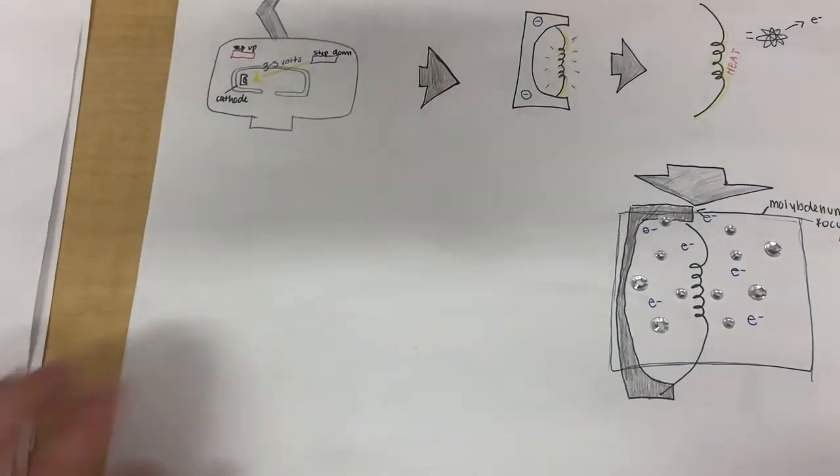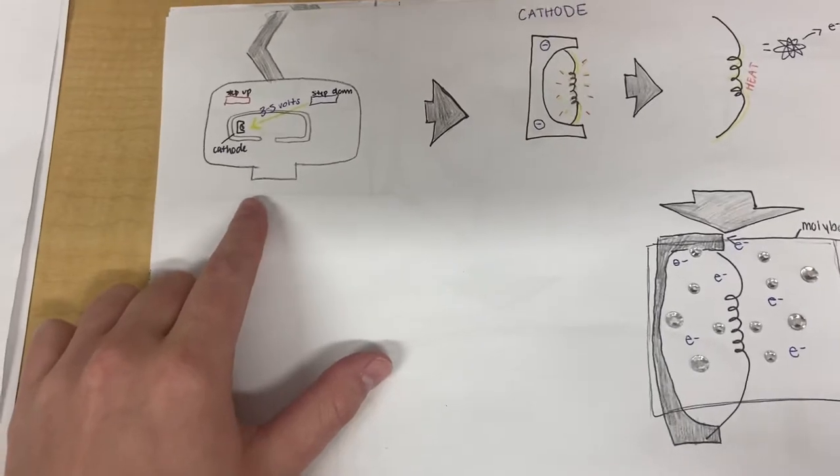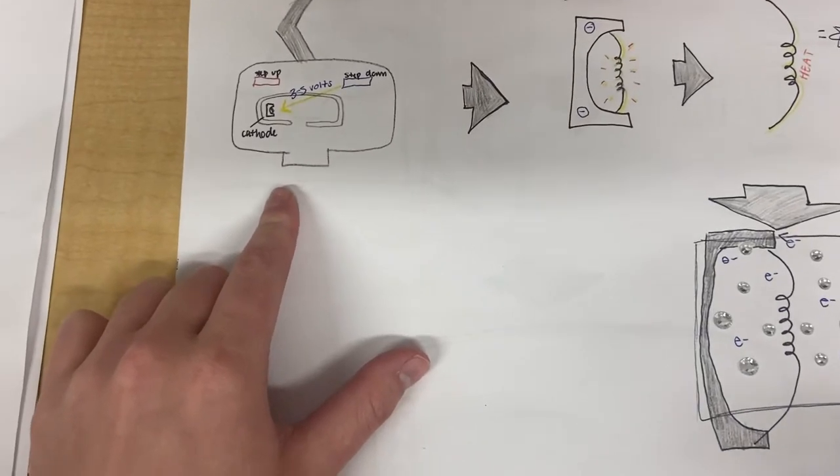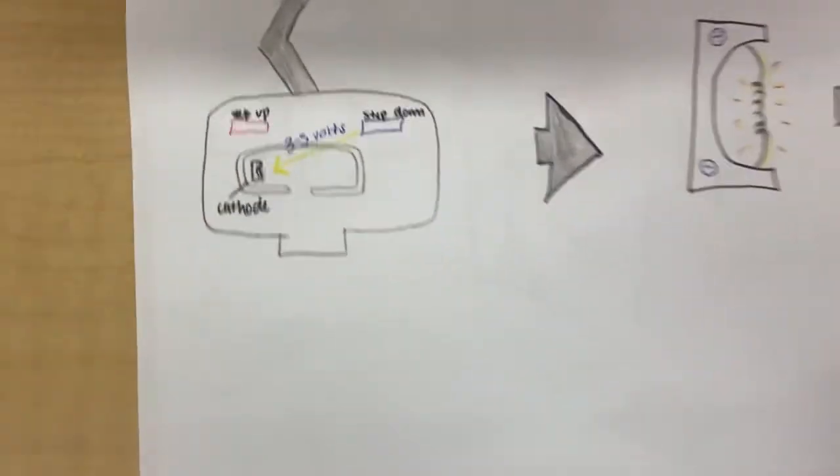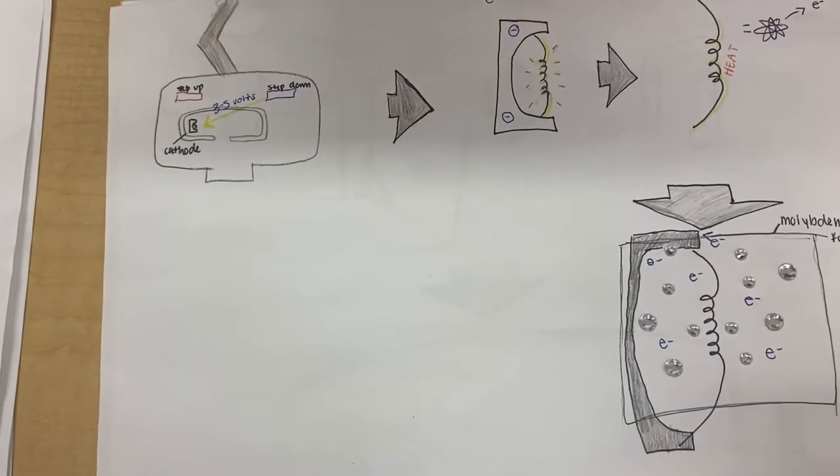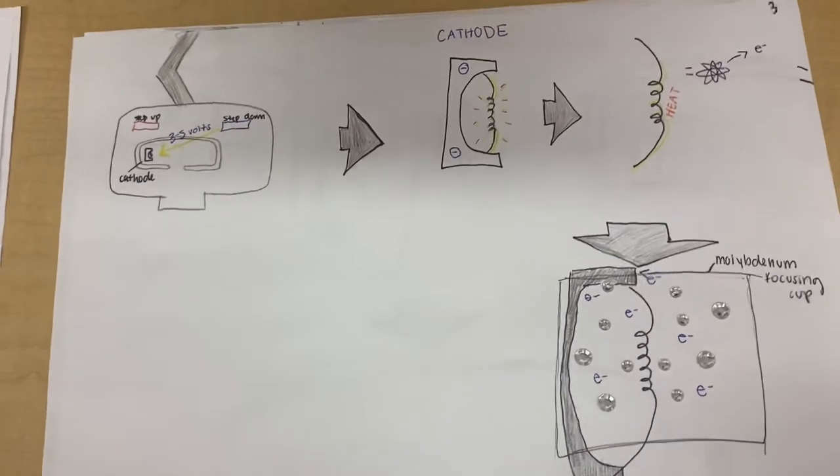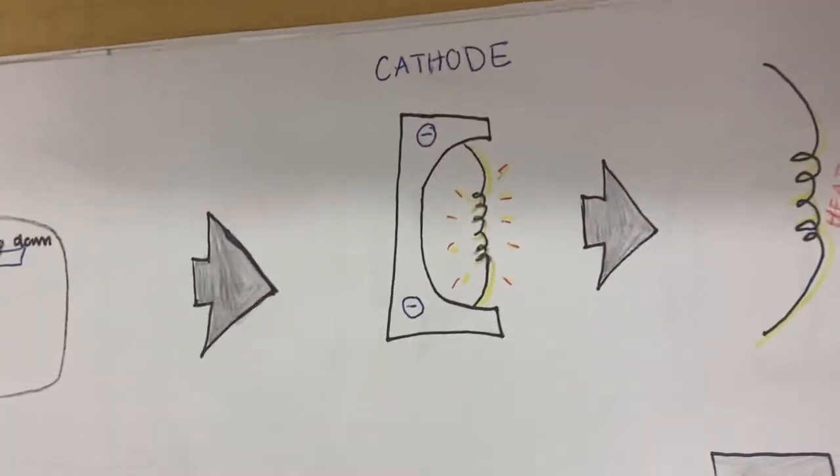Going on, the 3 to 5 volts will then enter the tube that contains the negative cathode, as you can see here. The volts will then heat the tungsten filament in the cathode and make the filament glow.